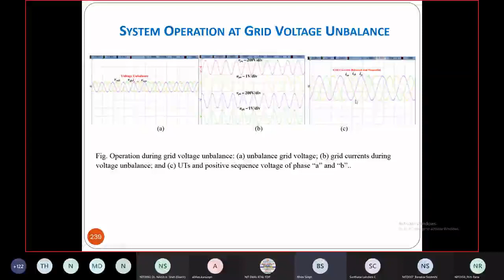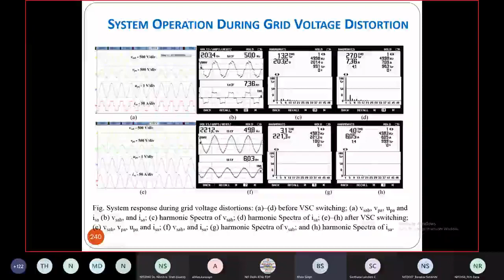In such cases, like in India, we have voltage unbalance and voltage distortion. We have to modify the control, typically for voltage filtering also, not only filtering the current. You can see how the voltage is distorted, with 13.2% THD, but the current THD is only typically about 4%. So virtually the control takes care of that. Your current THD still remains quite low.